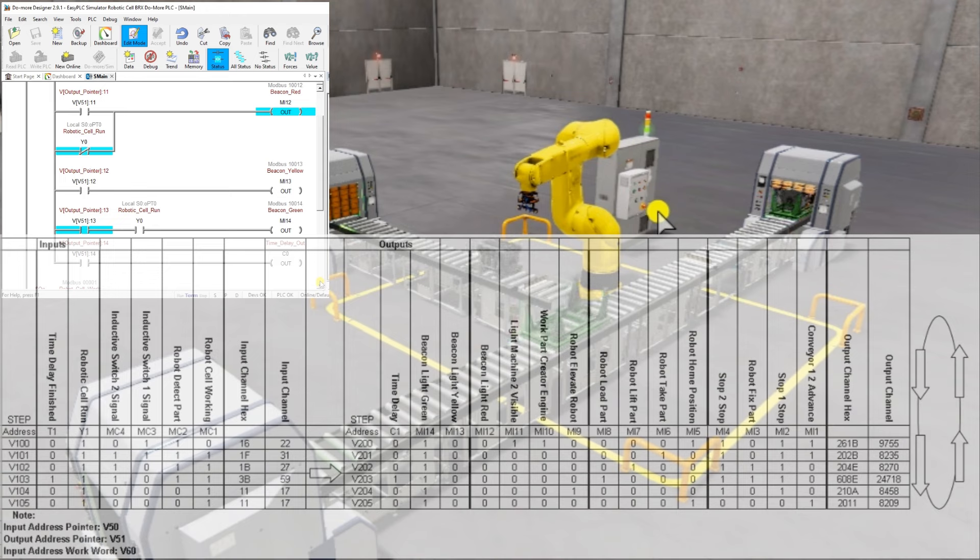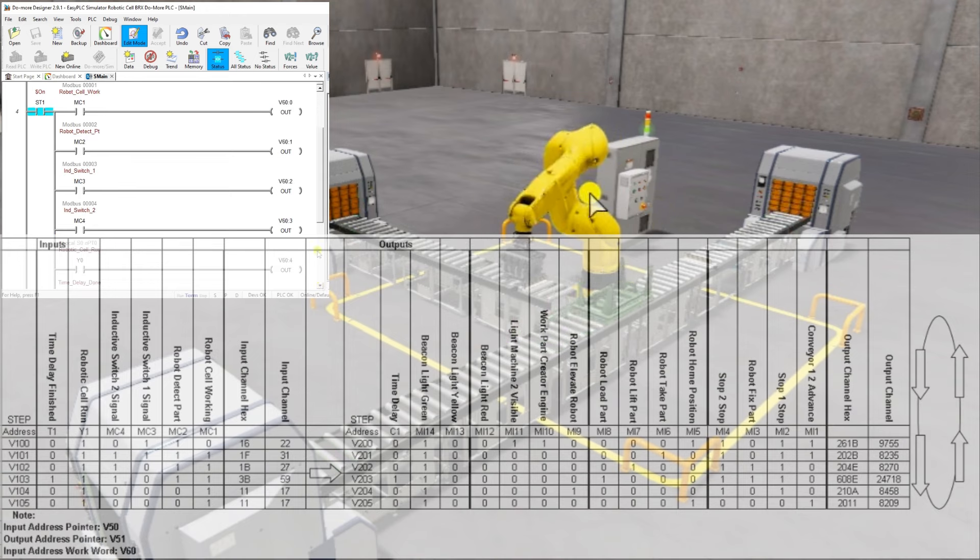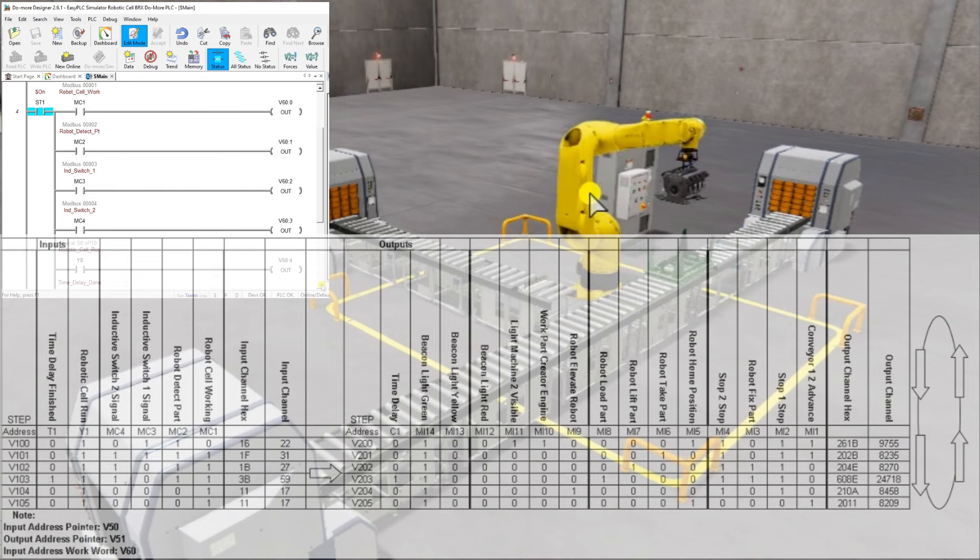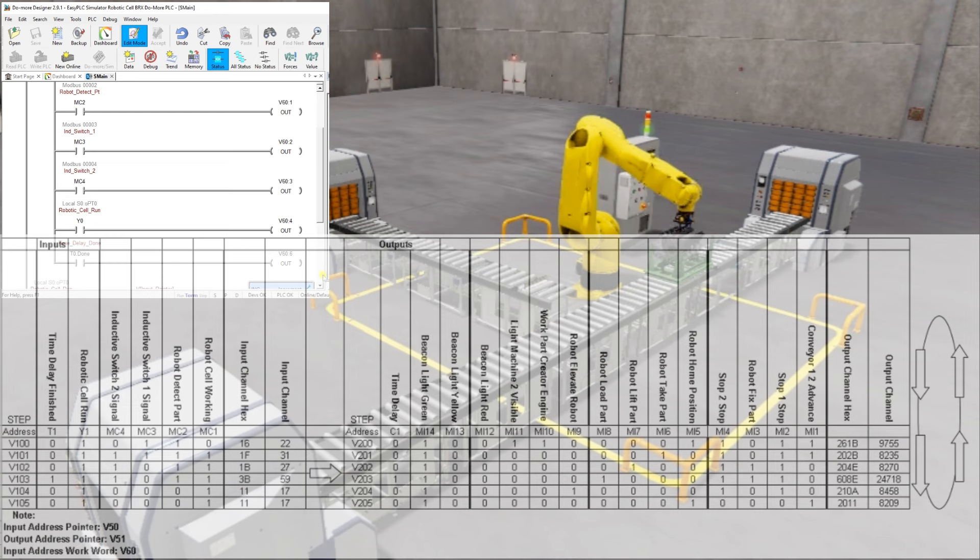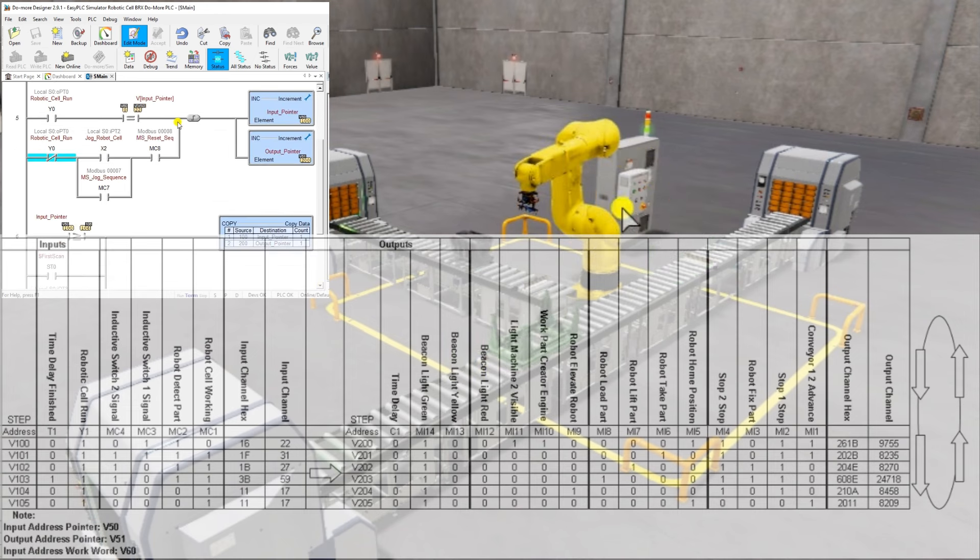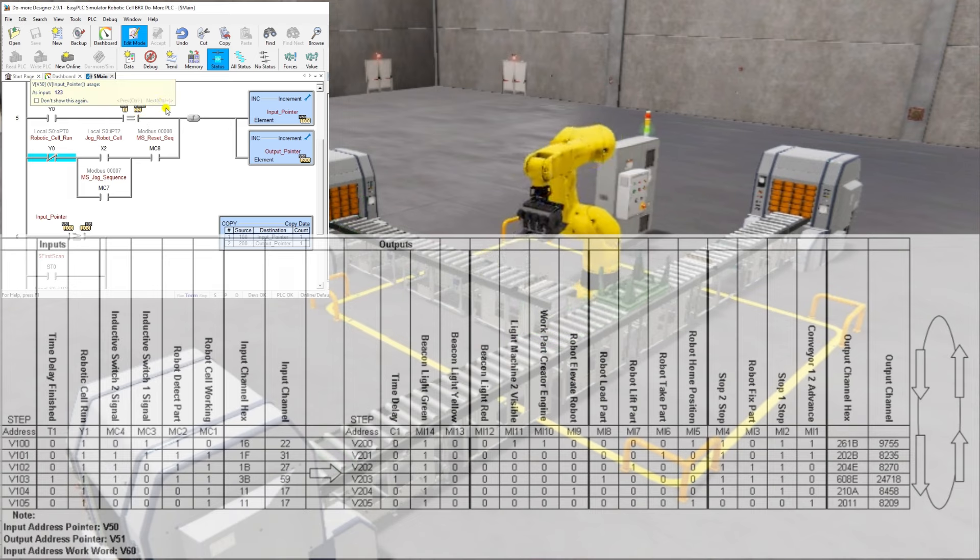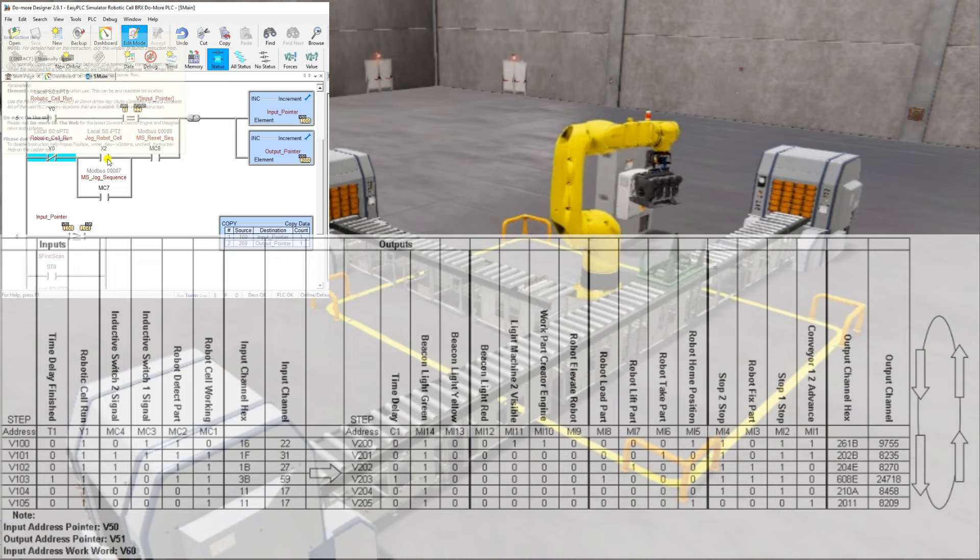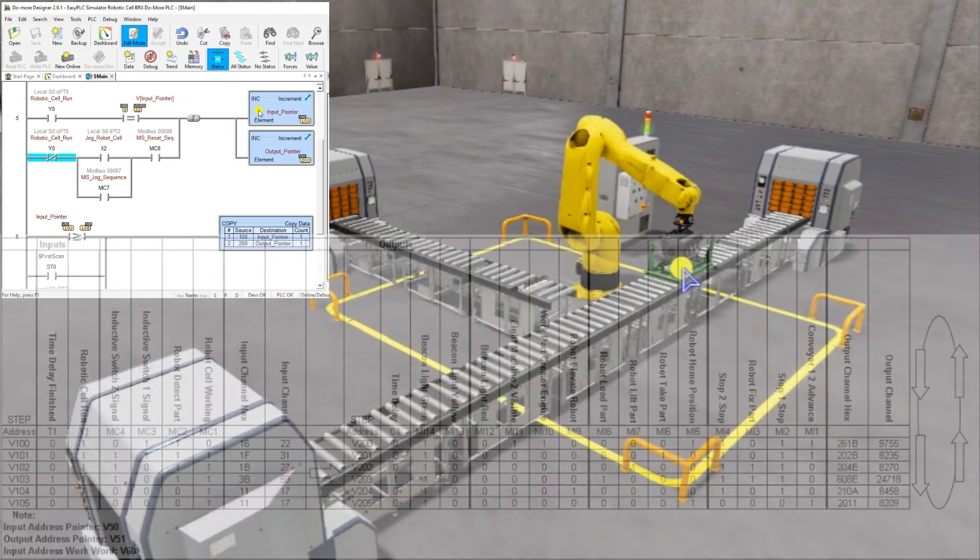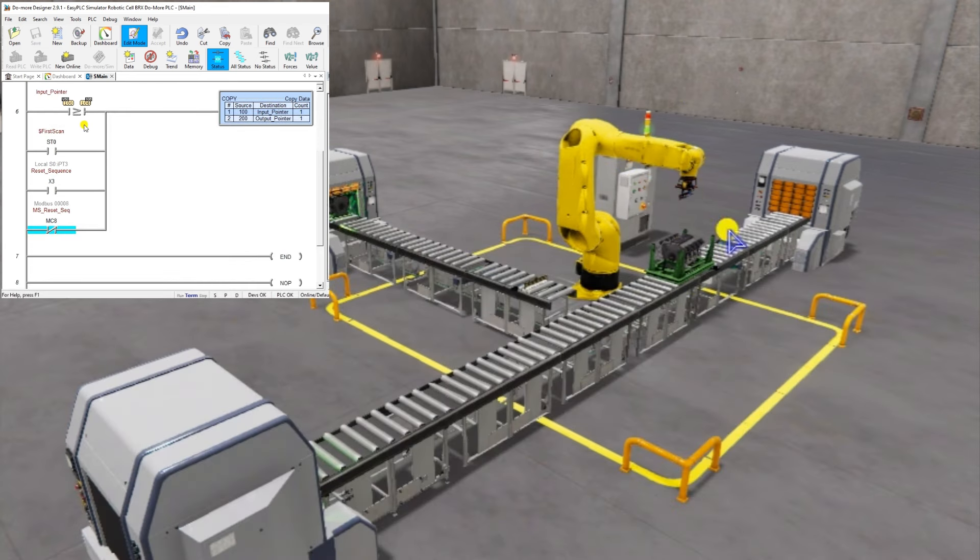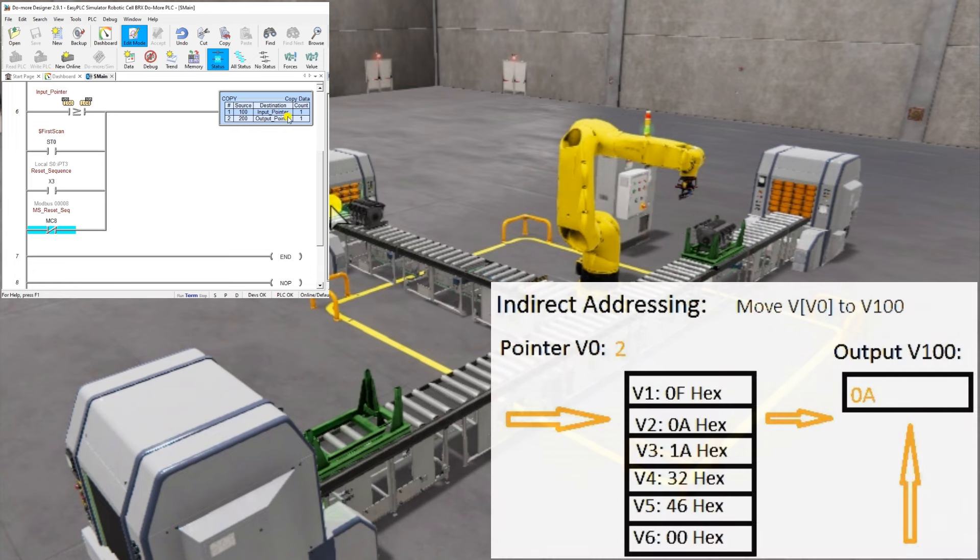They can be easily implemented in Click, Do More, and Productivity PLCs. Indirect addressing can take a sequence table and program it directly, comparing inputs to an input table and moving output table values to physical outputs. This method involves changing input and output tables to change the sequence of operations. Troubleshooting is made easy because pointers show table values versus actual input values. Indirect addressing can also be used to store values from a test in a series of registers in the PLC and to run stored recipes in a machine.